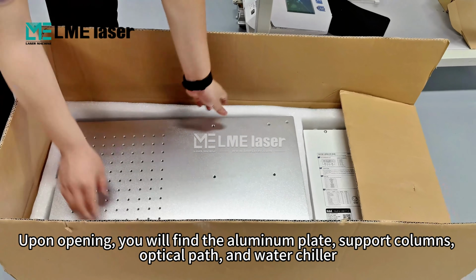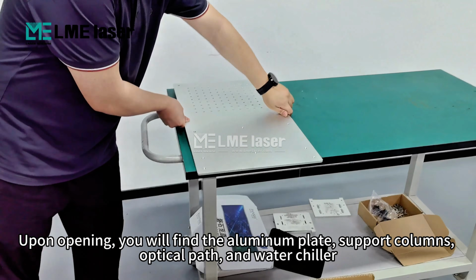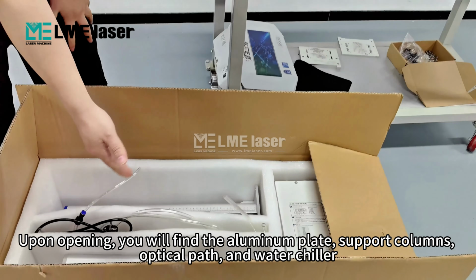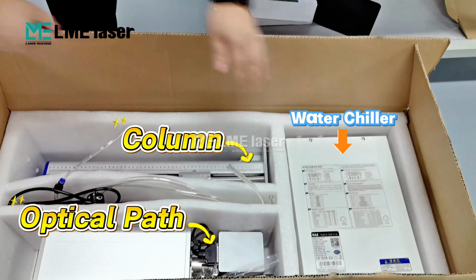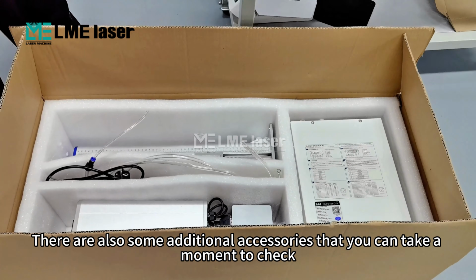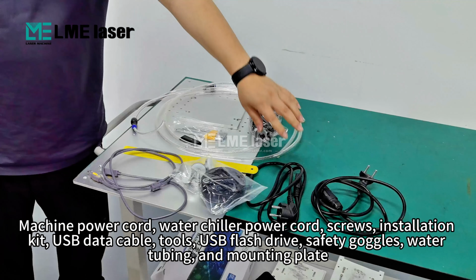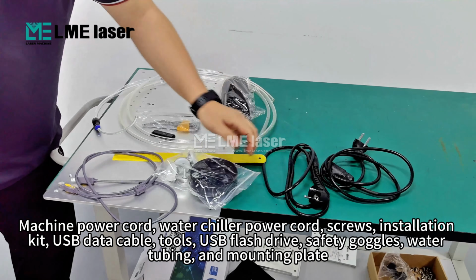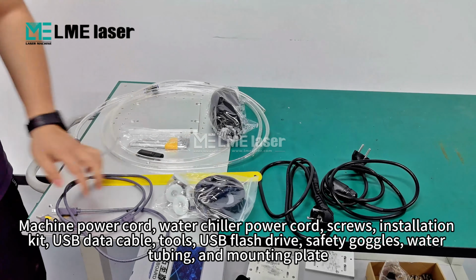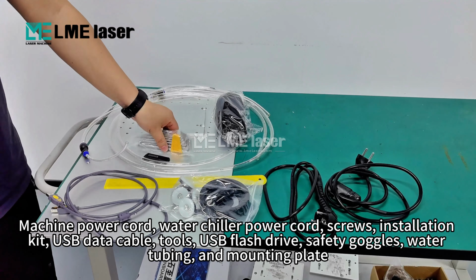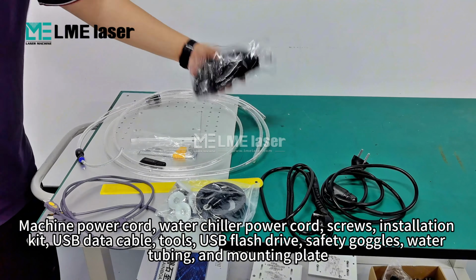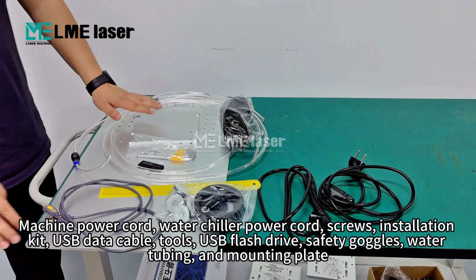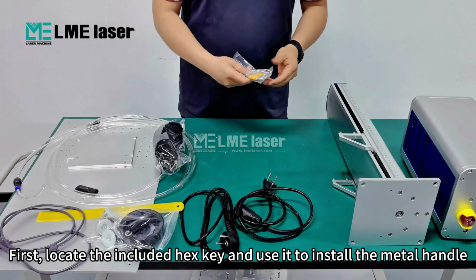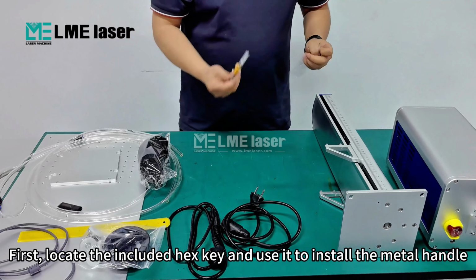Upon opening, you will find the aluminum plate, support columns, optical path, and water chiller. There are also some additional accessories that you can take a moment to check. Machine power cord, water chiller power cord, screws, installation kit, USB data cable, tools, USB flash drive, safety goggles, water tubing, and mounting plate. First, locate the included hex key and use it to install the metal handle.